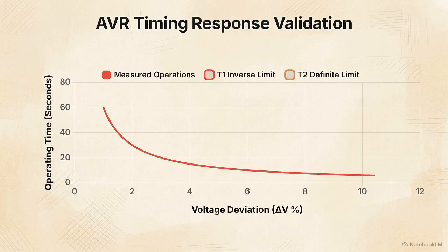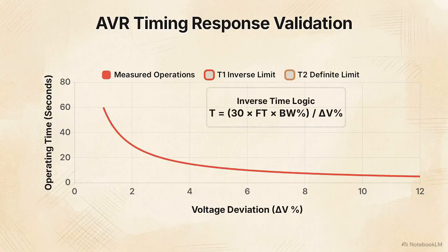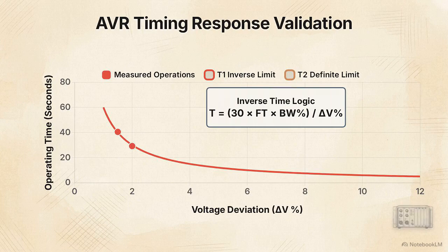Next, we test the inverse timer, or T1 function. This graph plots the exact T1 curve operation, utilizing secondary voltage deviation. The curve is calculated using this formula: 30 multiplied by the given time factor times the bandwidth percentage divided by the voltage deviation percentage.